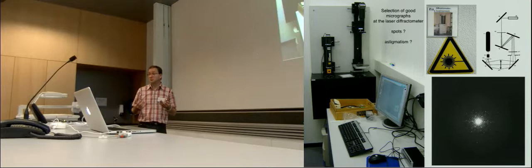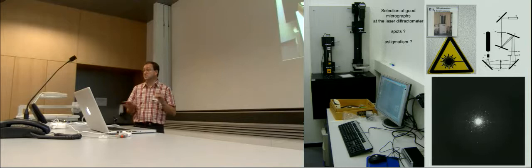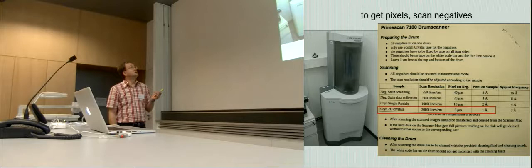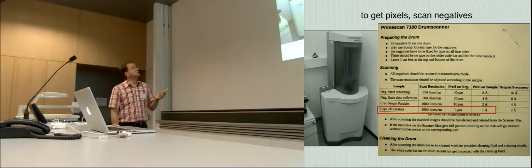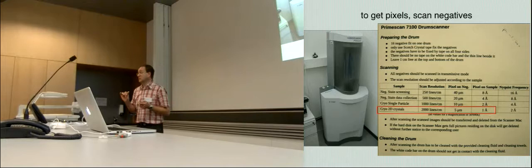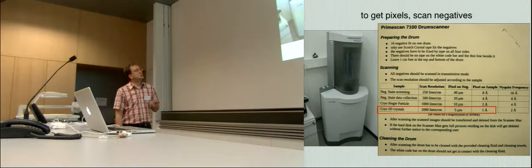And once you have the negatives, you go to a laser diffractogram. You can check if you have spots. If you get astigmatism, you can reject plenty of negatives without even scanning them. Only the very good ones that diffract, that you are happy with, go to the scanner. So we still have this scanner at CIC. It's a very good scanner. It's a prime scan. It is able to scan 16 negatives. And you would check the procedure. And for 2D crystals, you would scan at 2000 lines per centimeter, which is a pixel of 5 micrometers. So I'm starting to tell about pixels. This is now the workshop. And you get one angstrom on the sample.